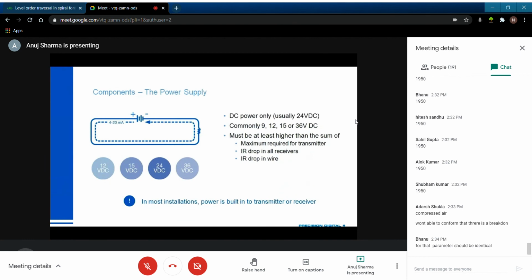The transmitter regulates the current in the loop. The power supply is what provides the voltage to make that current possible. Because remember, V equals IR. In order to have a current there, you've got to have a voltage. This is always going to be a DC power supply. When you hear 4 to 20 milliamps, what they really mean is 4 to 20 milliamps DC. And in most process applications, people use a 24-volt power supply simply because it's the most common and convenient. You could run into others, though.